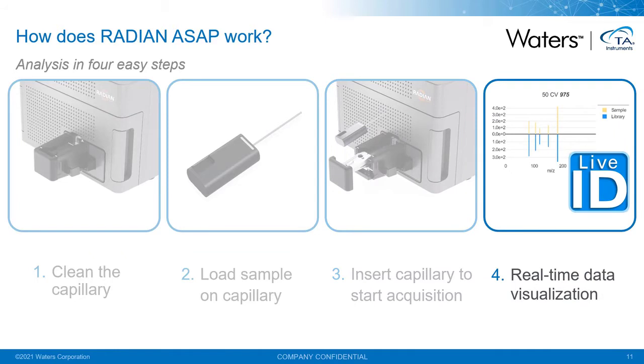Step four is getting your results. LiveID allows you to match your sample either against a library or a statistical model in real time, giving you library matches or sample classifications as you're running, depending on your chosen workflow. You can also use automatic processing via OpenLynx for a mass confirmation workflow, or with IonLynx to generate automatic reports based on ratiometric analysis or for semi-quantitative methodologies using an internal standard.